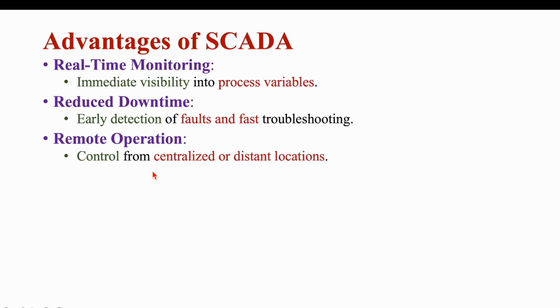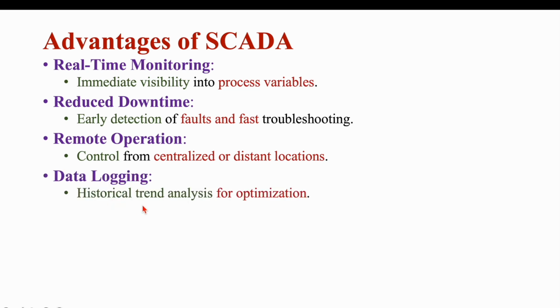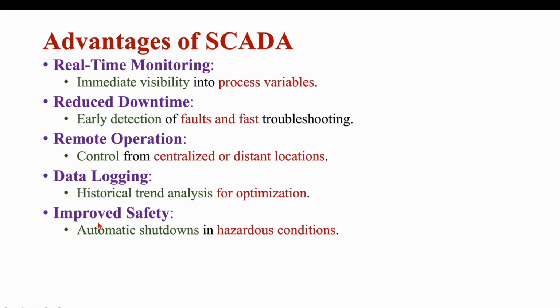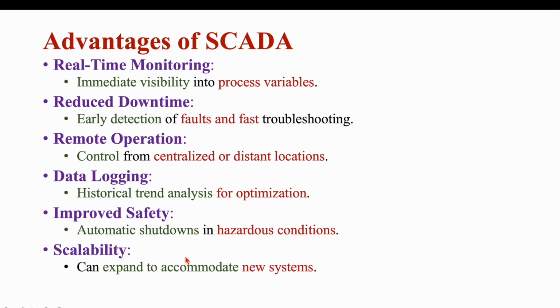Data logging provides historical trends and analysis for optimization, since all previous data is available for analysis or optimization. Improved safety means automatic shutdown in hazardous conditions - a very big advantage of SCADA systems. Scalability allows the system to expand to accommodate new systems.